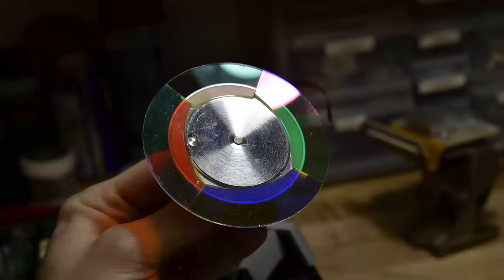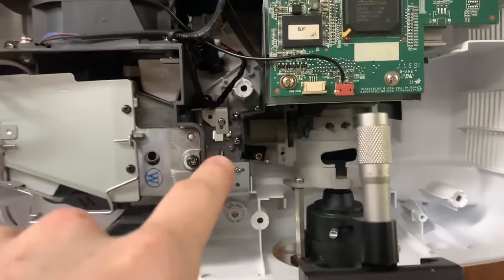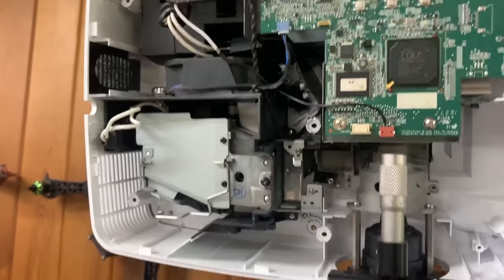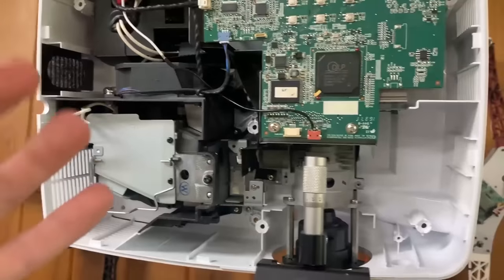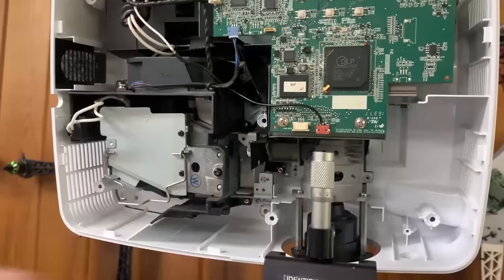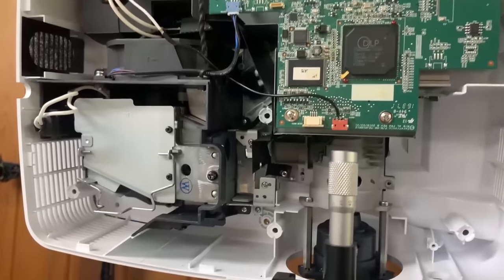First of all, I've removed the color wheel, which normally sits in here, and it attenuates quite a lot of the ultraviolet going through this path. We want to get as much UV shooting down through here and exposing onto the wafer as possible to keep the exposure times low.